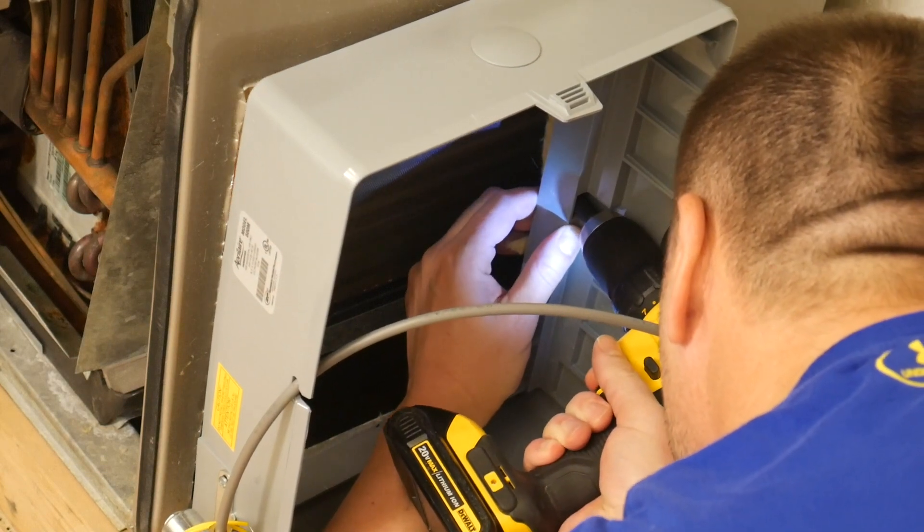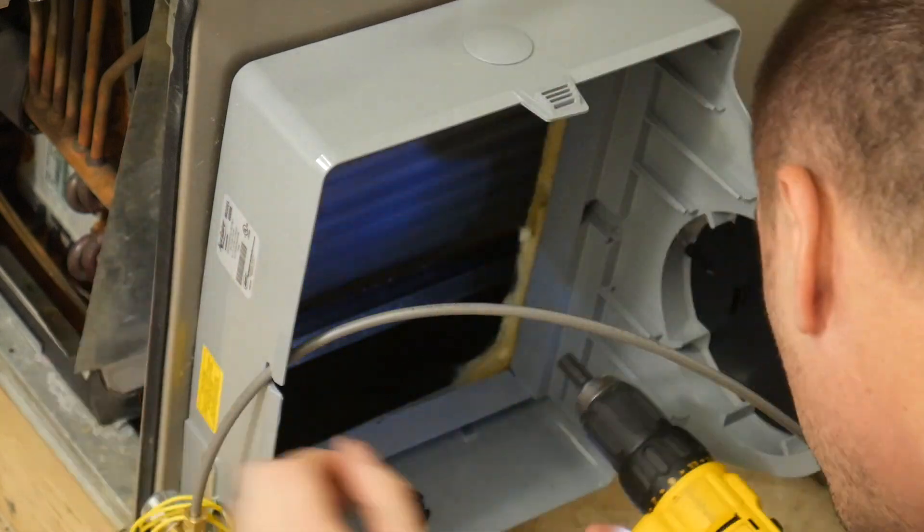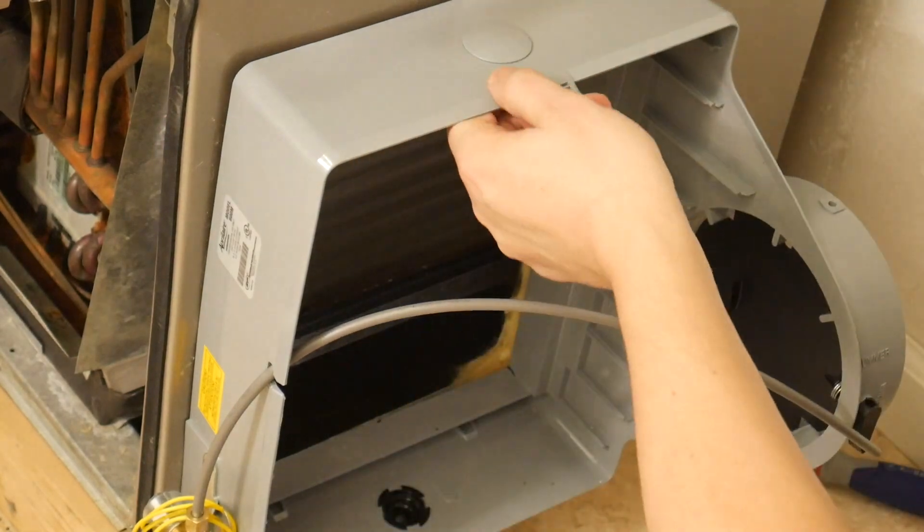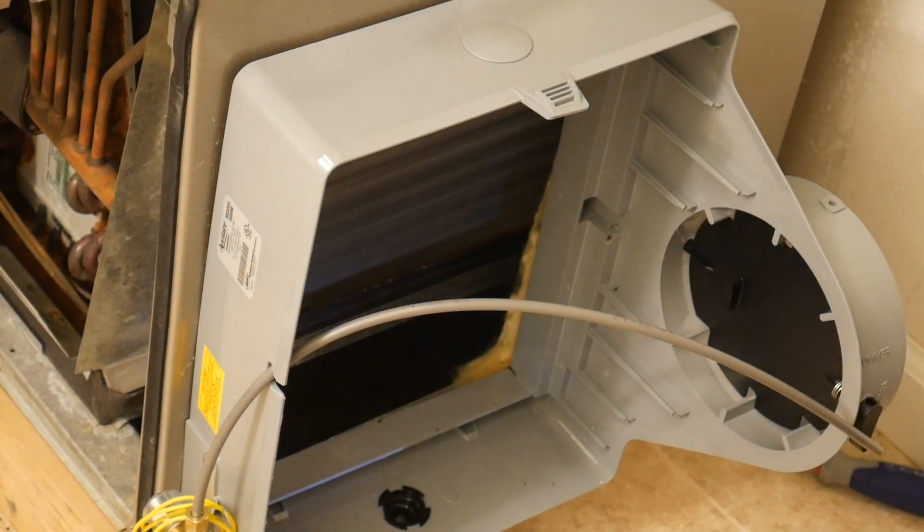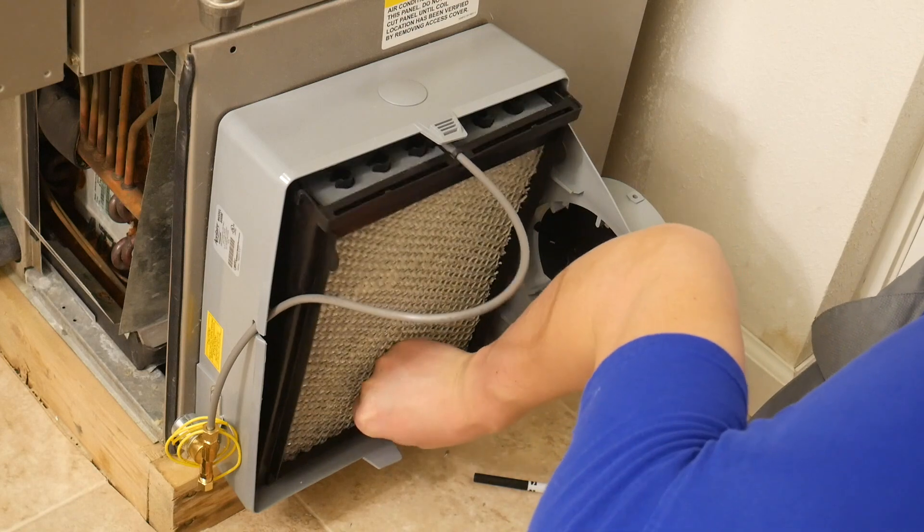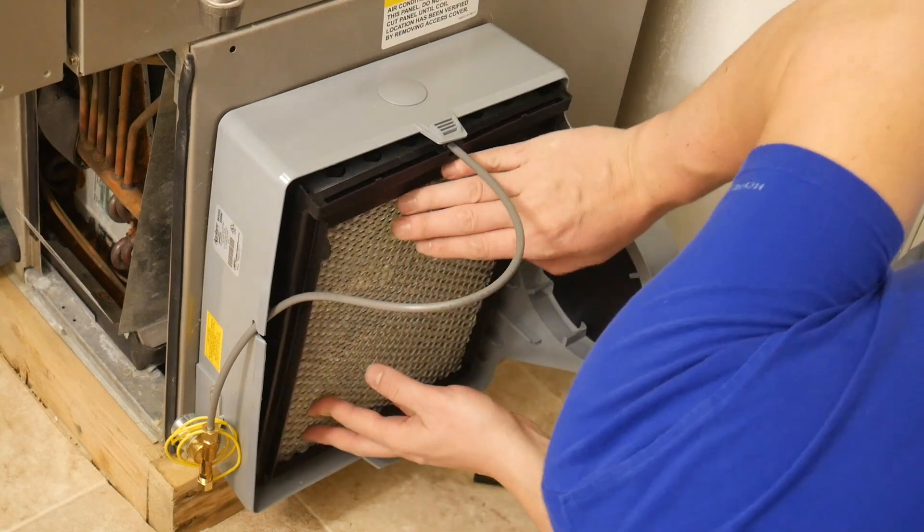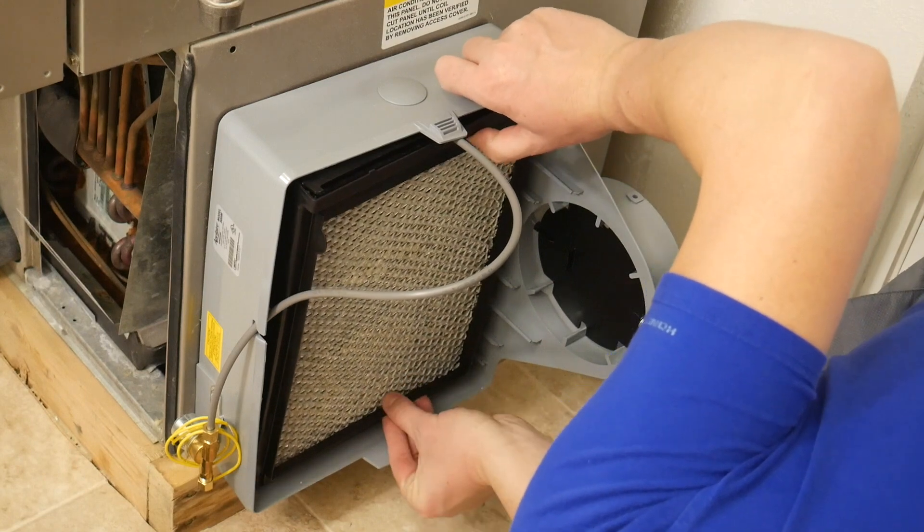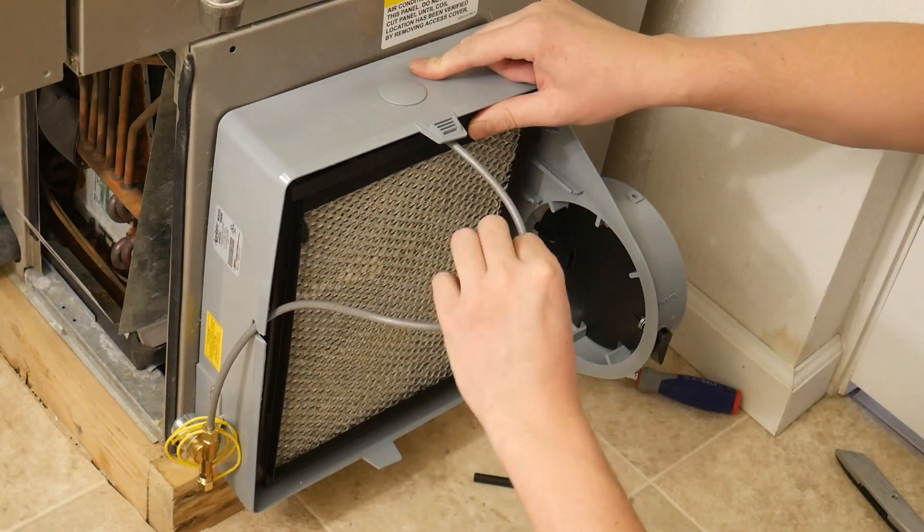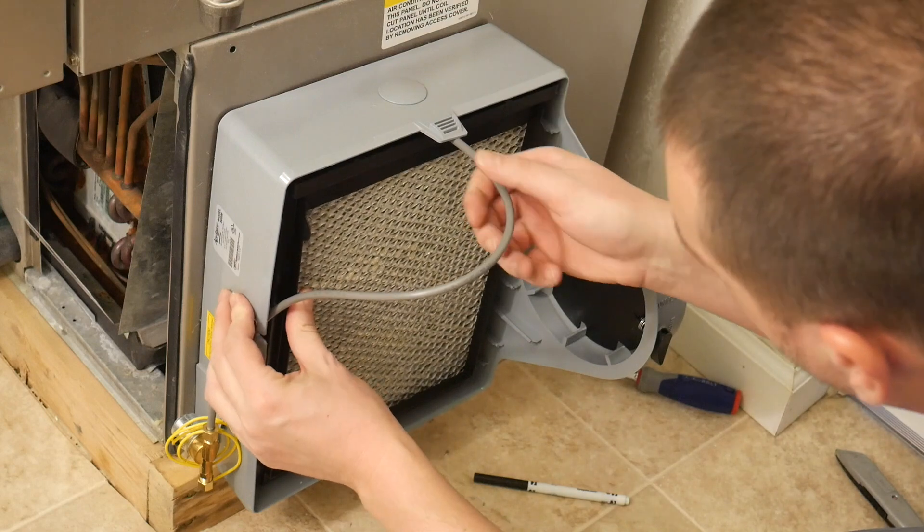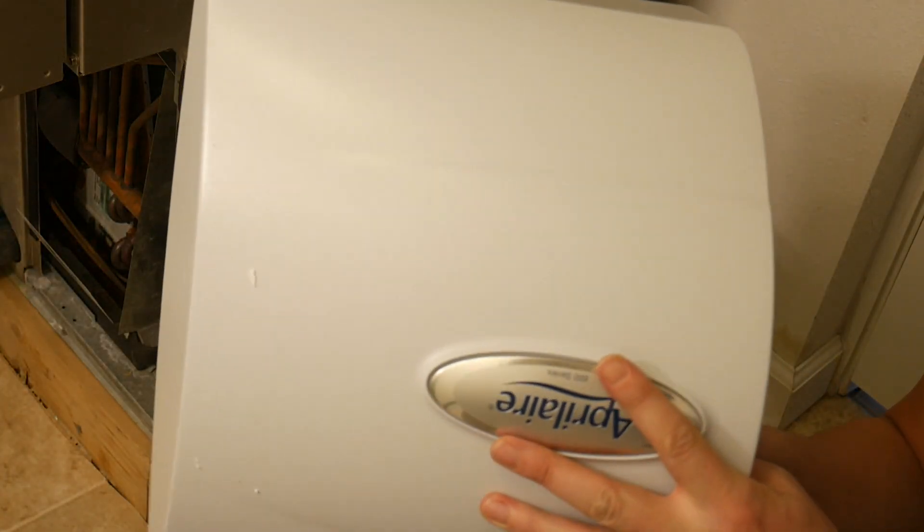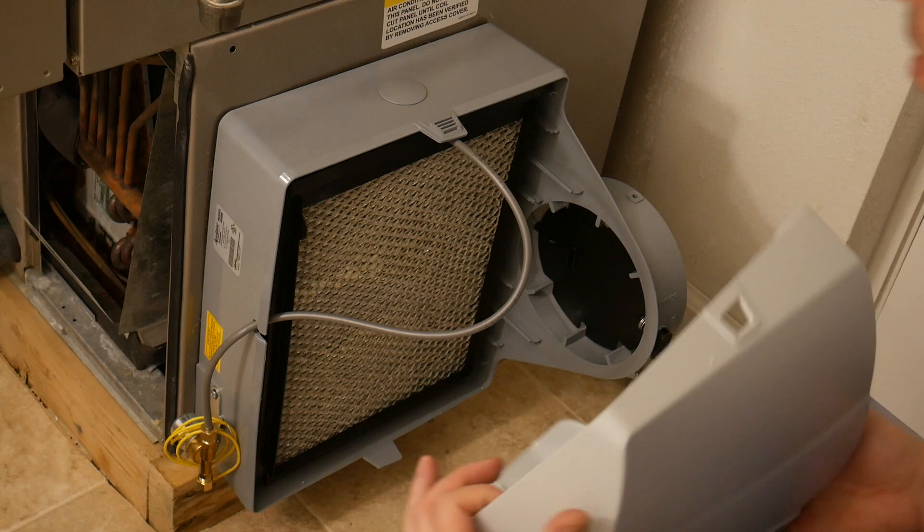And this unit doesn't come with screws or any kind of hoses. So you got to pick it up yourself. You can even use some regular screws for this setup. Now make sure the filter, the nozzle go inside on the bottom in that hole. It goes through and then it needs to click on top. That way the water on this, the gray hose, the water comes in and it spreads it apart, spreads it all the way around the filter. And when the warm air blows from the inside of the furnace, it will go back into the system. It will kind of circulate.